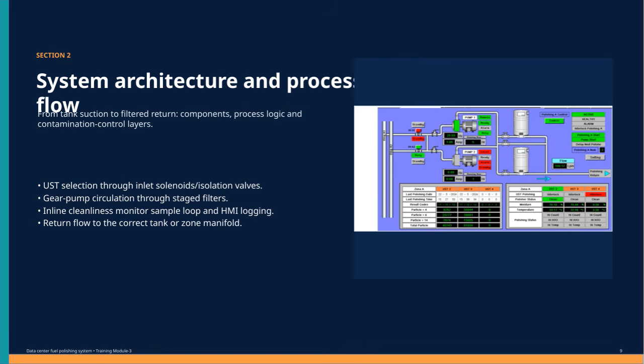First, the process begins with selecting the appropriate underground storage tank, or UST, using inlet solenoids or isolation valves. These components ensure that fuel is drawn from the correct source without cross-contamination. Next, the gear pump circulates the fuel through a series of staged filters. These filters progressively remove contaminants to protect the fuel system and maintain optimum cleanliness. An inline cleanliness monitor is incorporated within a sample loop to constantly assess fuel quality. This monitor, along with the human-machine interface or HMI, logs the data for real-time tracking and record keeping.